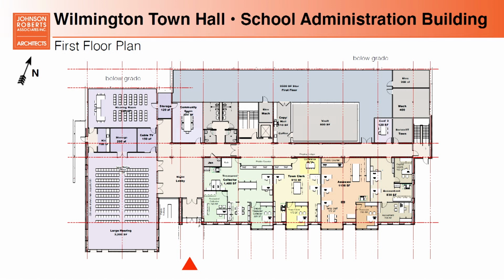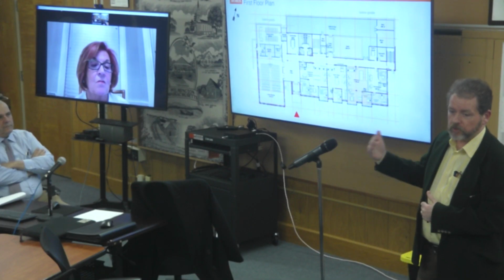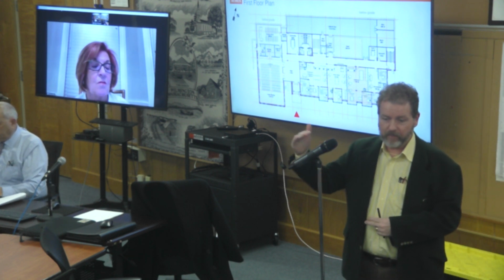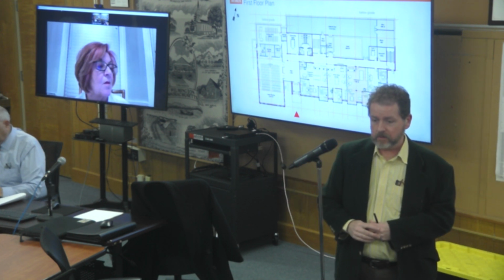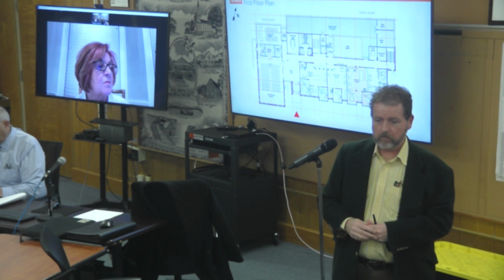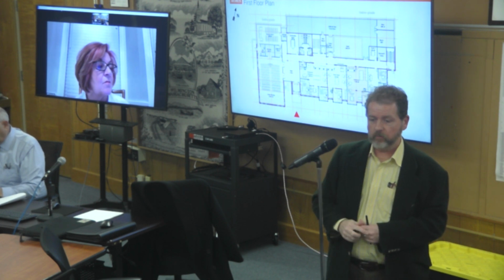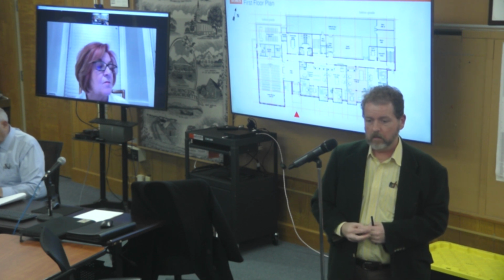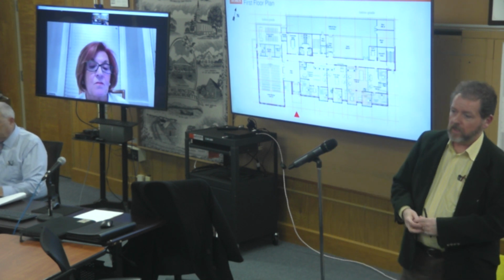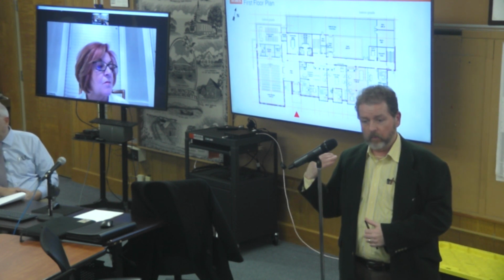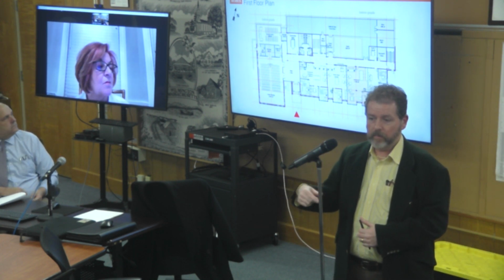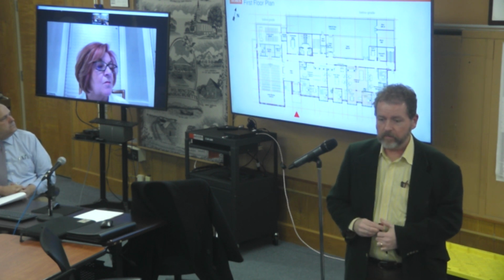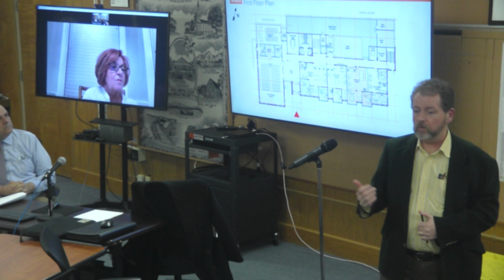Yes, in a word. When the mechanical, electrical, plumbing, and fire protection engineers come present, they'll talk to you about that. They'll size the building for additional capacity - additional capacity in all the panels, in the switchgear, and they'll size the generator and transformer for additional capacity as well, so you'll have room for growth. Even if you later decided to pull that transformer off and put a bigger one on, there'll be spare conduit running to the street so you can do what you need in the future.